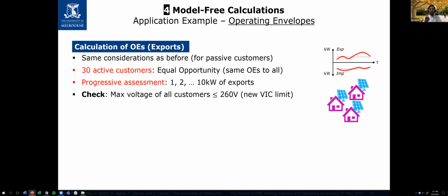The operating envelopes we consider are equal opportunity, meaning the same operating envelopes for all customers. This is just for simplicity and to illustrate the case. So we make a progressive assessment of export for our active customers, assessing 1, 2, up to 10 kilowatts of export. Again, the check is to see if all voltages are within statutory limits.